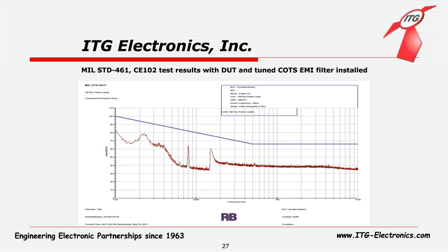All right. And let's see, Rafik is asking, is the ambient noise test really necessary in case of a conducted emission test? As I think that is required for radiated emissions only. I like to say, no, it's not necessary, but it's one of the first things one should do, because the shielded room is clean, yes, but the power, depending on what type of power supply is used, and if the power supply power is not clean, you're not going to get good results.